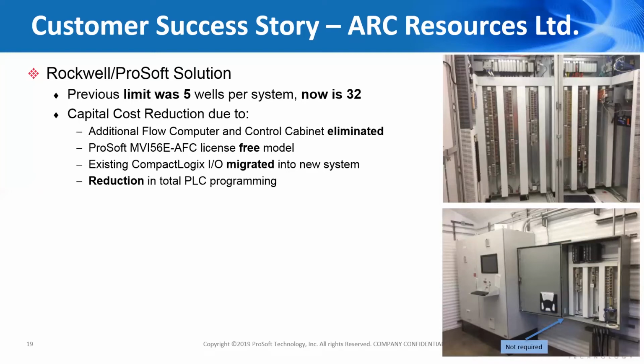They were able to realize that benefit because the in-chassis flow computer is a co-processor unit. As they needed additional metering points on a well pad site, they could simply add another ProSoft AFC module into the chassis, expanding from 16 measurement points off one card to a total of 32 measurement points.